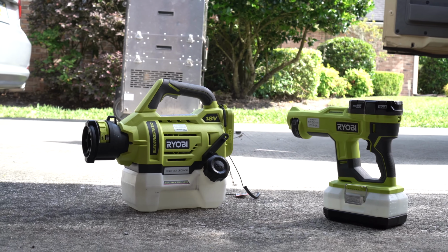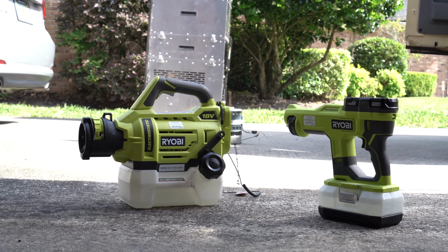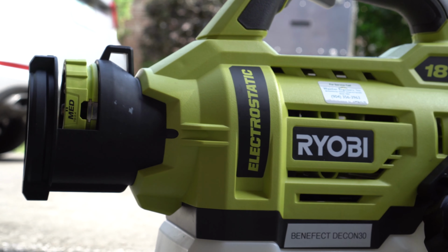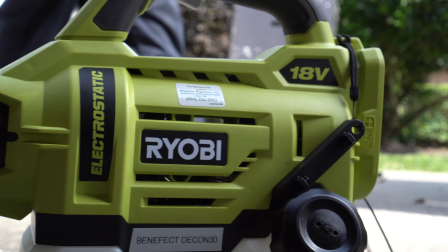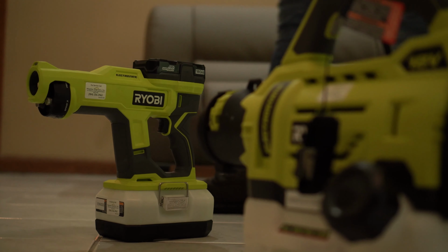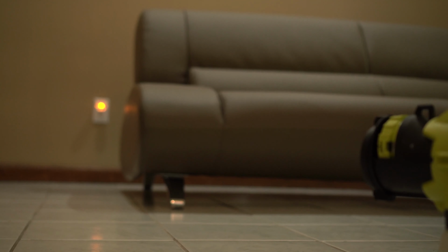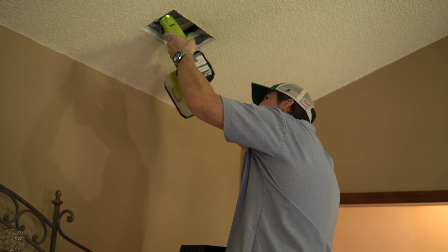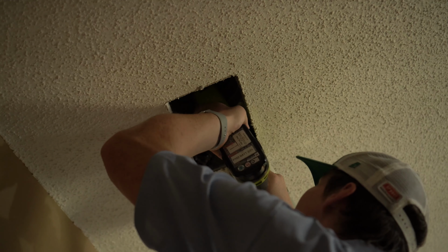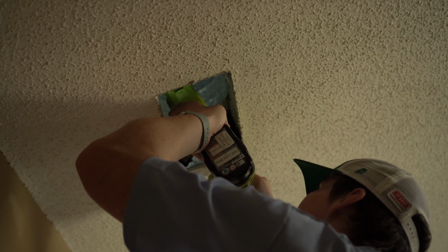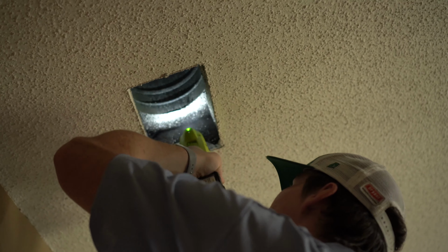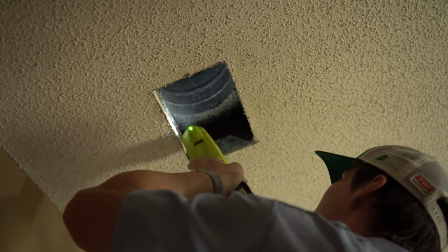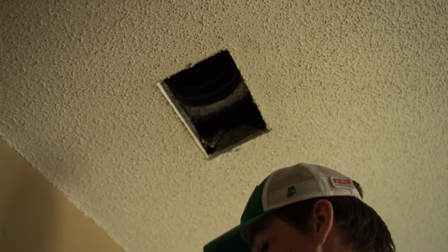After completing the air duct cleaning, but before you reinstall the grills, while the abatement machine is still running with suction to the supply side, go to each supply vent and fog an approved solution into the system using a duct fogging machine. Fog each supply until the solution is close to forming a droplet of solution from the duct boot where the flex or metal connect occurs. This will ensure a proper amount was used in each vent and that the process is consistent for each vent.